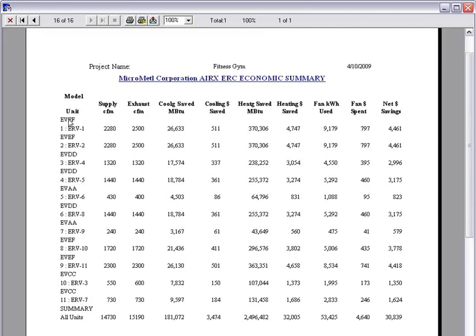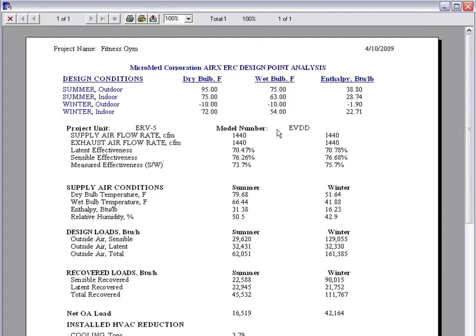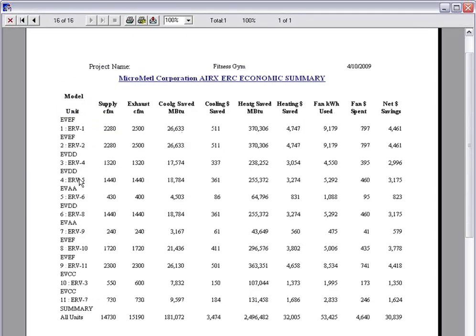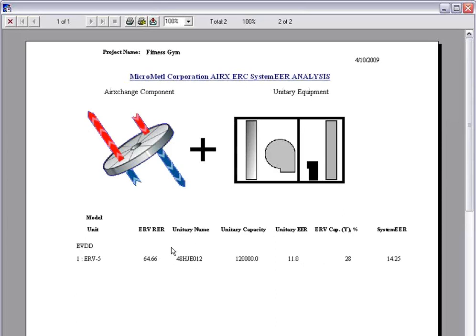MicroMetl Corporation would take that air exchange data on the wheel, use it in their combined cabinet. So once we combine that into a cabinet, that EVDD wheel that we talked about in that previous slide, we would combine that with the specific cabinet from MicroMetl, and then we would have our complete combined energy savings, our cooling savings, our heating savings. A heating savings is basically the amount of energy that we're able to extract out of the exhaust air. But that translates as savings because that's less heating that the HVAC system has to do. So we save energy on the HVAC system, and that's where those savings come in.